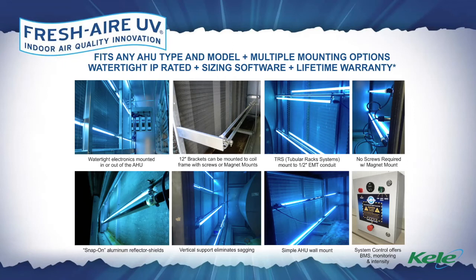So the radiometer is measuring the UV intensity, the irradiance, in real time. And should anything happen to a lamp, if the irradiance drops below a predetermined level, it'll notify through either the control panel or BMS that there's an issue.